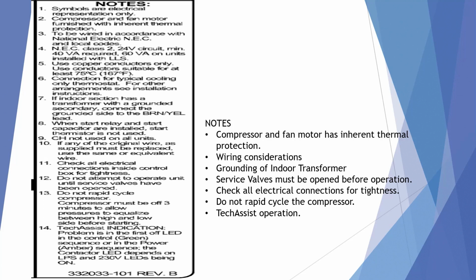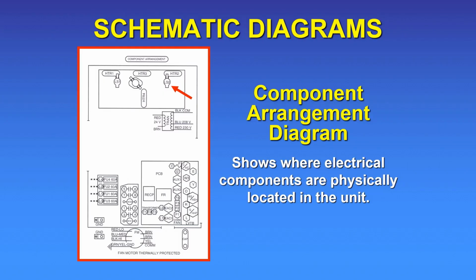It also gives you wiring considerations, the size of wire that is needed for this unit. It tells you that the service valves must be opened before operation, that you should check all electrical connections for tightness before operating the system, and that you should not rapid cycle the compressor. This particular unit has what is called a tech assist operation, which gives you various fault codes for various faults on the system. So the notes will give you some very important information that is necessary for troubleshooting or properly operating the system.